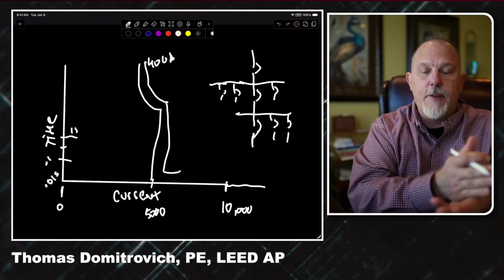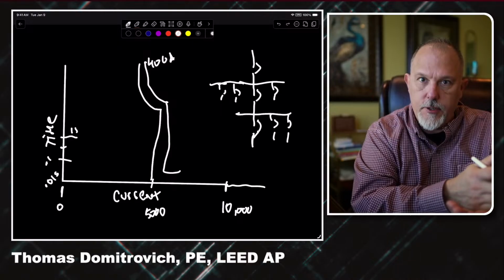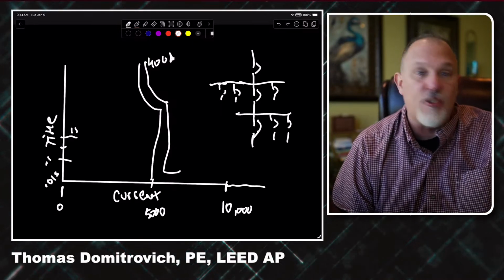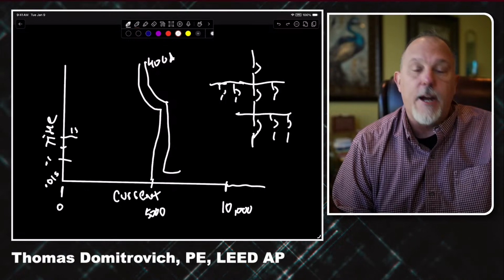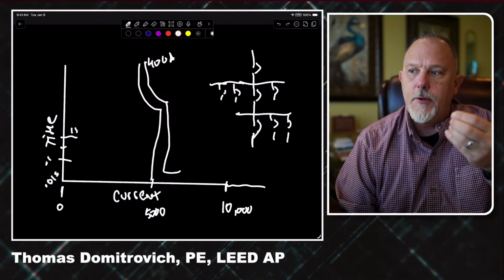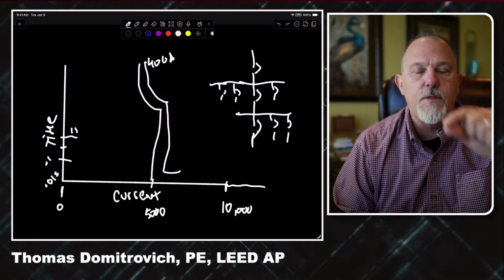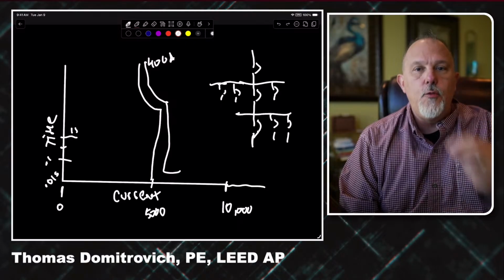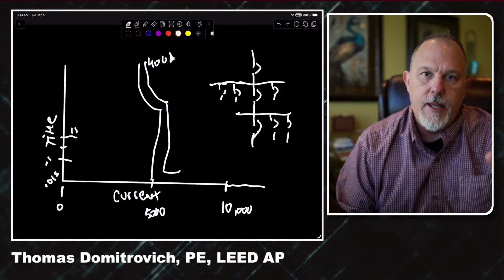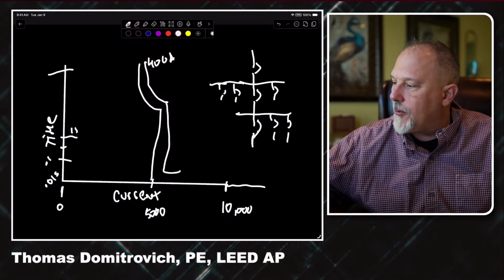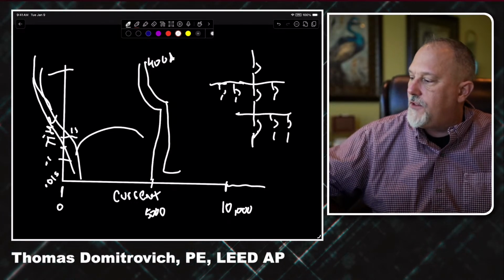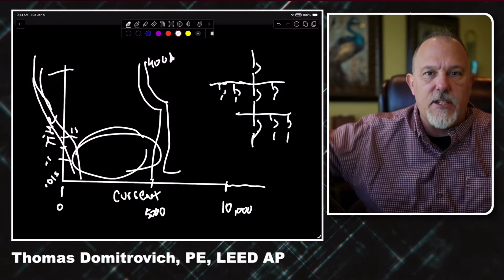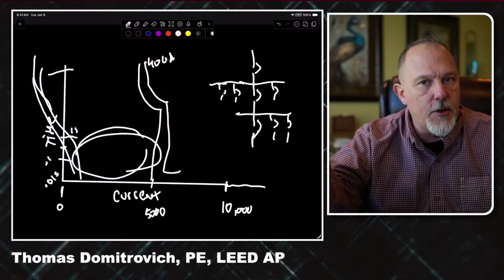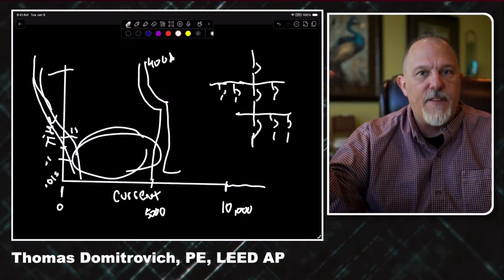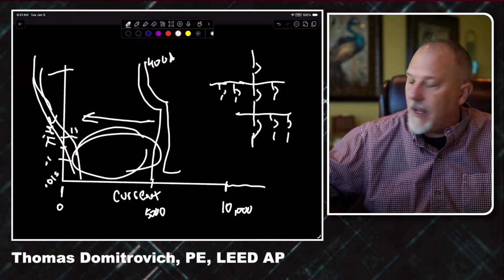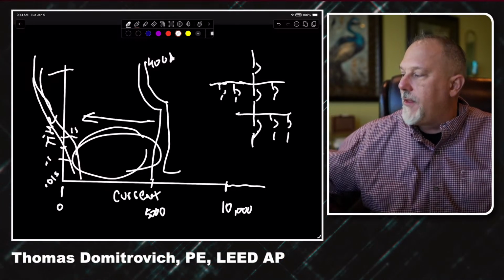You want very fast operations close to the load. That's why we put current limiting devices inside of electronics and other equipment. They'll use fuses. They'll use electronic fuses. They'll use fuses that mount to the circuit boards. You want a very fast response time. And what that does is, if your fuse is operating way over here, that gives you all of this no man's land, all of that space to be very flexible on that very first overcurrent protective device upstream. And if I can move that very first device as far to the left as I can get it, it gives me breathing room for the next one up.